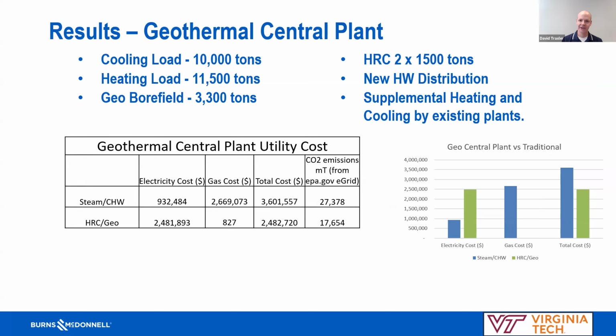So even though our plant is only about 1/3 the size of our load, we provide almost all of the heating for the buildings throughout the course of the year. You can see the graph on the right, where you have the heat recovery chiller Geo in green, how the gas cost for that is not even showing up on the graph. It's less than $1,000 compared to $2.7 million, or what they were paying for in steam.